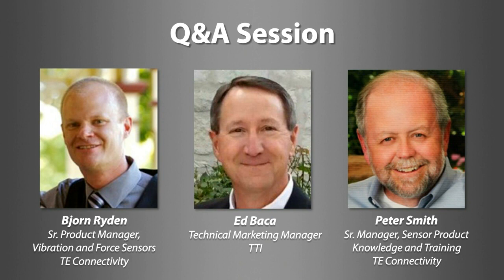So it's important to recognize that every sensor, to operate properly, must be connected intimately to the phenomenon that you're trying to detect, trying to sense. And if you introduce a conformal coating, that actually isolates or insulates the sensor to some degree from the phenomenon that you're interested in. Some of our sensors, it's not a problem. As Bjorn pointed out, the accelerometers, there's no problem because we're monitoring vibration, which passes through conformal coating with no trouble at all. But some of our sensors, you need to approach those with caution in applying the conformal coats. I hope everybody understands that.